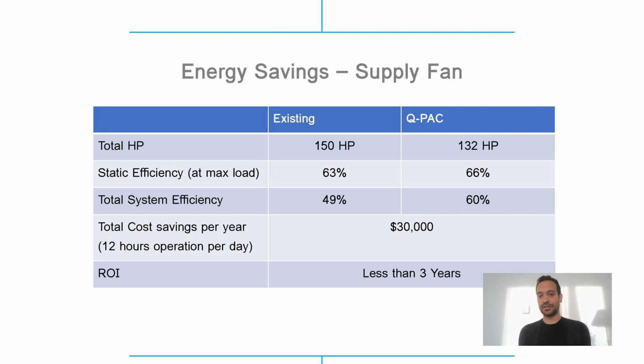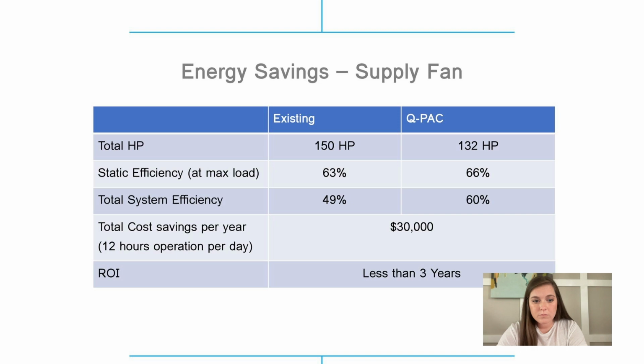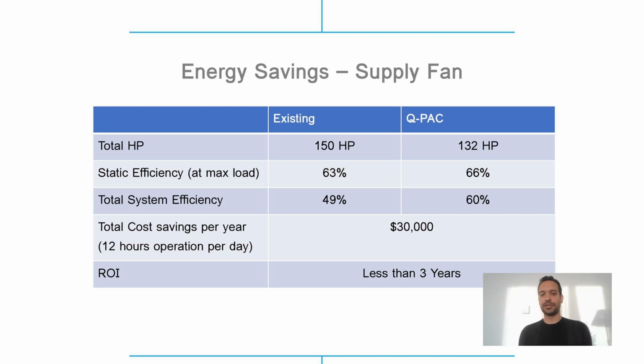The existing supply fan was 150 horsepower. We replaced that with a smaller horsepower on the supply fan for us. So the combined horsepower of our fan array was 132 horsepower. So we went down, which is what we expect when we replace these induction motor fans with our EC motor fan arrays. We expect that reduction in horsepower. This was pretty high static. I think we went up an inch here. So we went up to 8 inches of static on the supply side. So when we go higher static, we get closer to the existing fans. As you see, it's not as low. It's like we reduced 20 horsepower there.